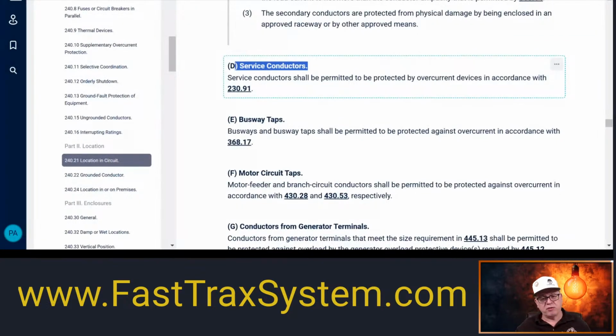So one of the allowances, for example, in a 120/240 volt where we have the service drop coming down, we typically would say those conductors have to be the same ampacity as the device it terminates into, and they have to have the overload protection in 230. Well, we have an allowance there. Remember to use 310.12, which is the 83% rule. So those conductors may not have the same ampacity as the device they terminate to, for example, services.